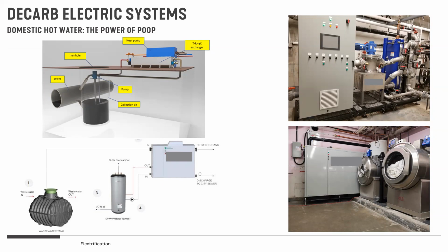There's a couple of systems on the market that essentially take all of your waste into a tank. We then use a system to pump out that waste, and it goes through what we call a macerator - think of it as a blender for sewage. It chops up and cuts up everything into a slurry, runs that through a heat exchanger, and then dumps it back into the sewer. The heat pump is just stealing the heat from that slurry in the heat exchanger. So the poo water, if you will, never comes close to the domestic hot water - there's a heat pump in between.